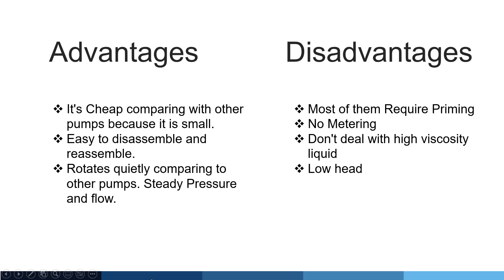Now we will see the advantages and disadvantages of the centrifugal pump. Advantages: it is cheap compared with other pumps because it is small, easy to disassemble and reassemble, rotates quietly compared to other pumps, and provides steady pressure and flow. Disadvantages: most require priming, no metering, cannot deal with high viscosity liquids, and produces low head.